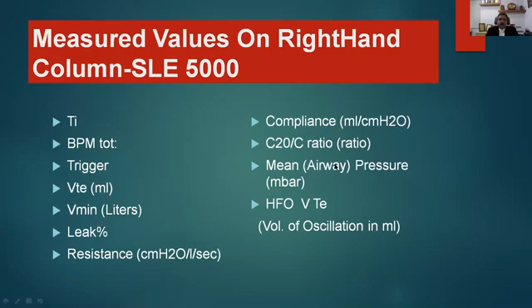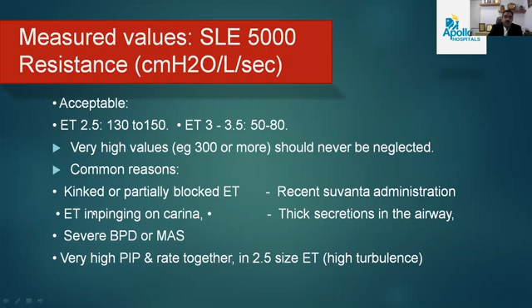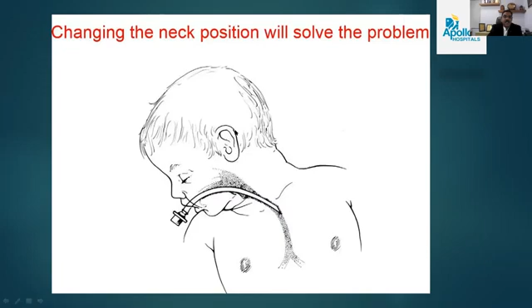If this resistance is above 300, that means there is a kinked or partially blocked ET, the ET is impinging on the carina, there is severe BPD or MAS, recent surfactant administration, thick secretions in the airway, or a very high PIP and rate together, and if you are using a 2.5 size ET, this causes high turbulence. So these are the conditions. If there is a resistance of more than 300, you should get alerted to one of these problems. This is what happens if the baby is flexing its neck: the ET can get kinked, and by changing the neck position, the problem will be solved.